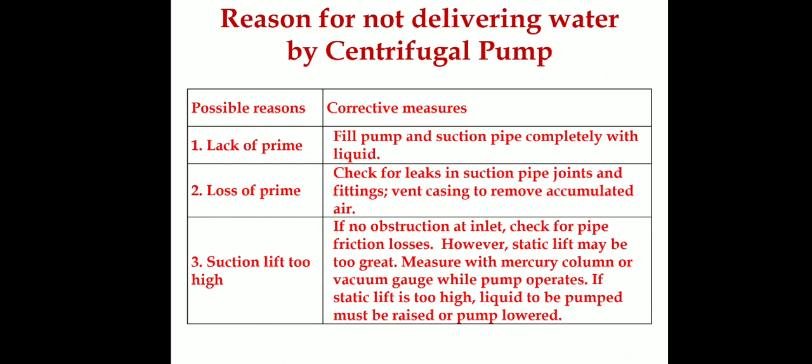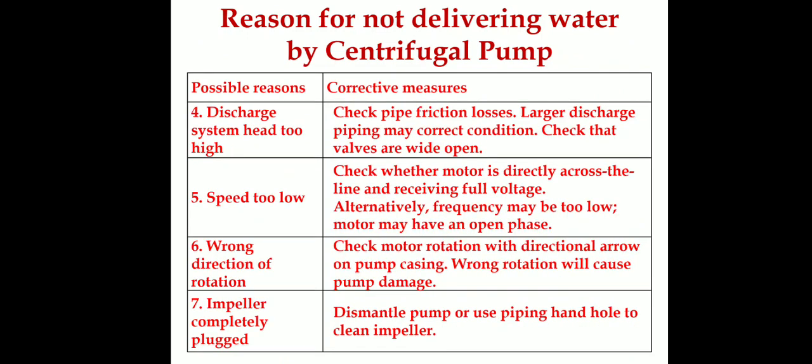We also have to look into suction pipe friction. The fourth cause is discharge system head too high, which occurs because of friction in the delivery pipe. The valve should be completely open to reduce friction and optimize the delivery system.